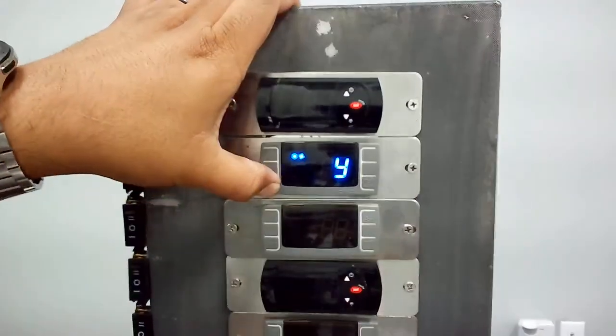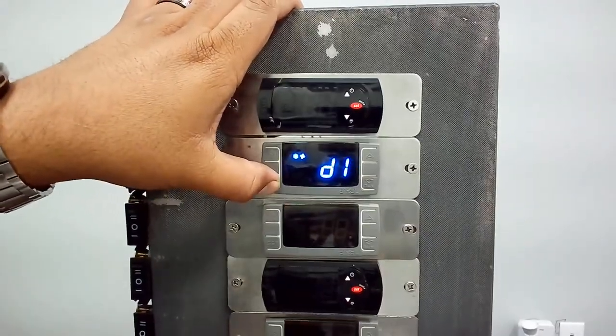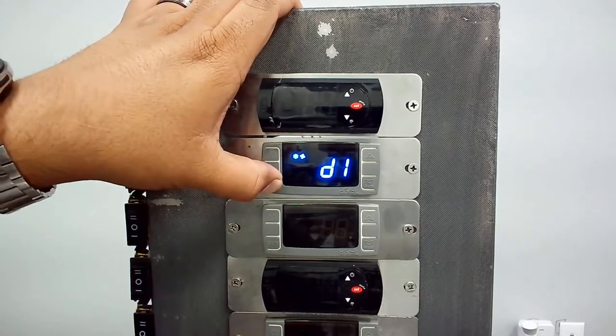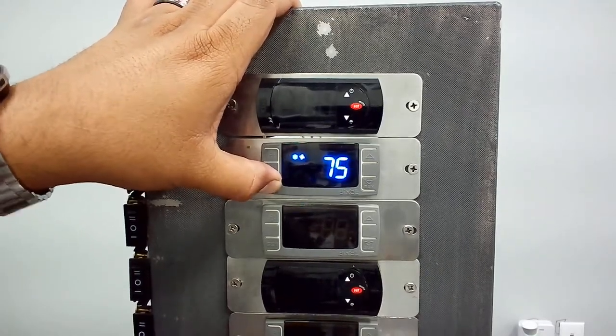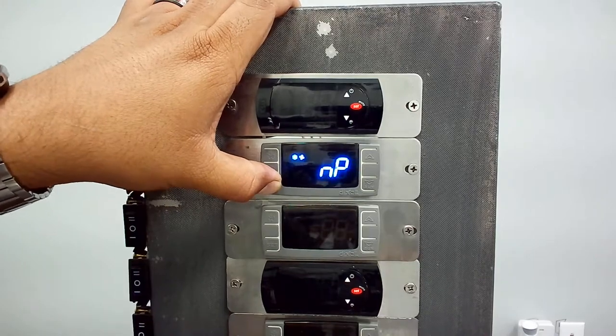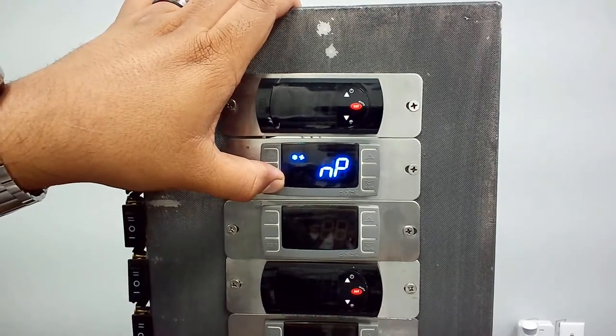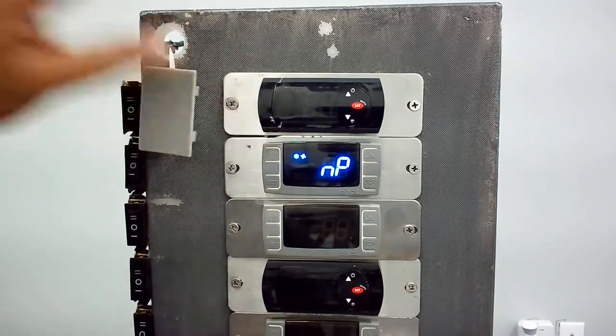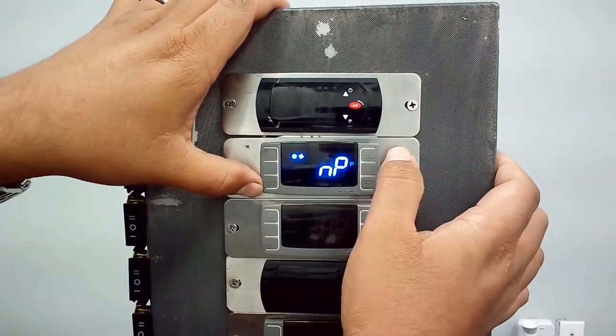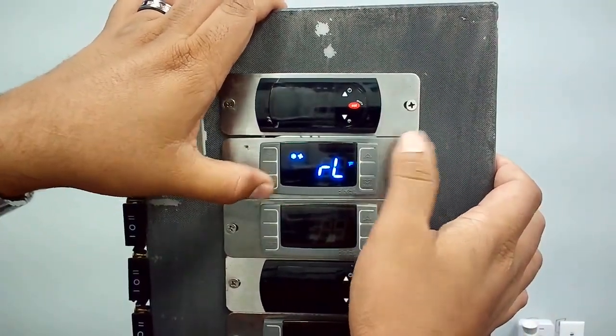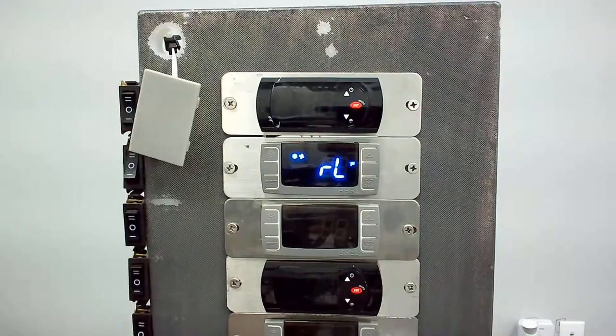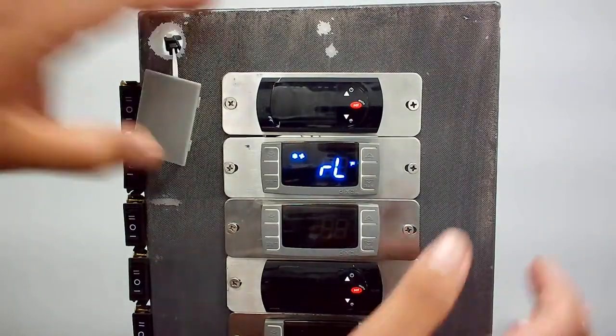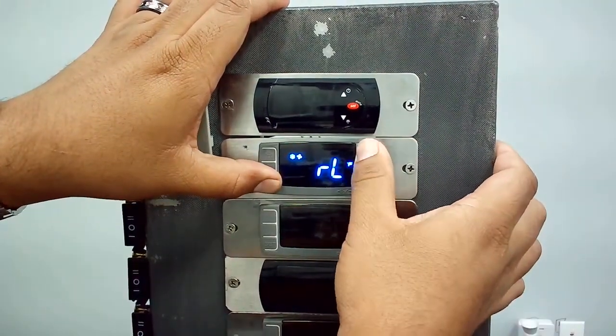Once you get through these, you're going to see D1 and D2. These are not settings, these are readout only. So this will tell you what the probe is actually reading. D2, no probe, because this is a refrigerator that doesn't need a secondary probe. Once you go through all this, you can actually just leave it alone. It'll reset on its own after about 15 seconds. Or you can hold down the set button and hit the up arrow.